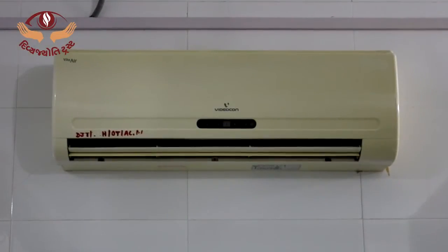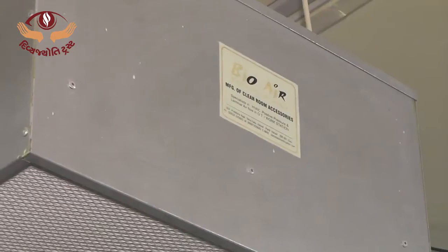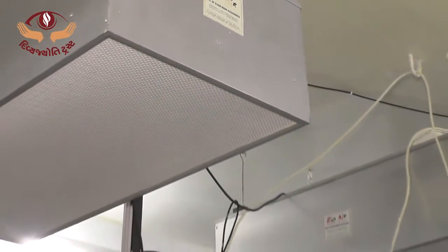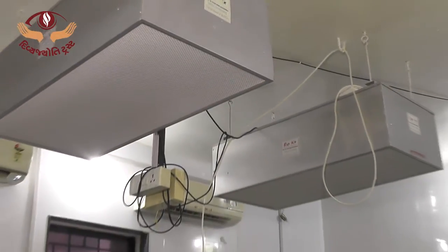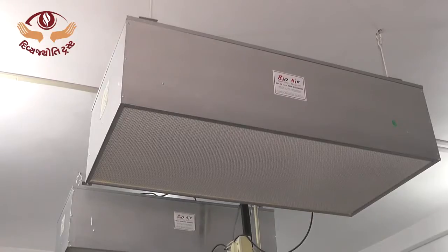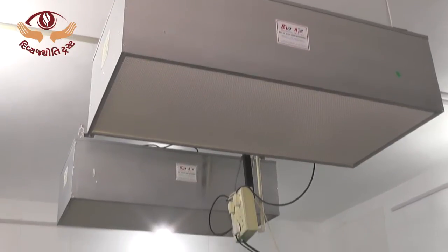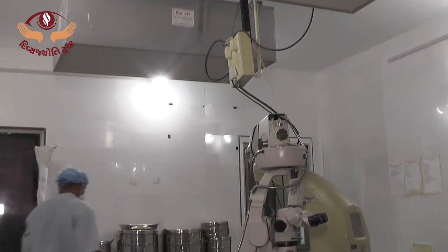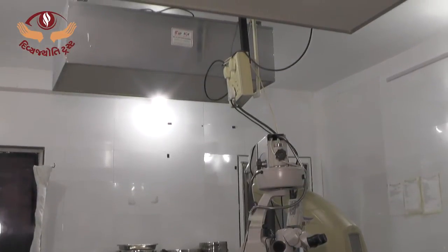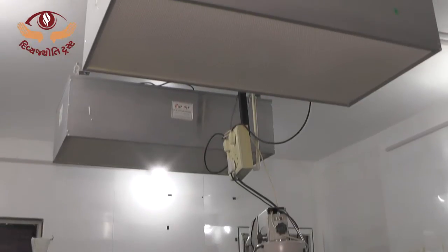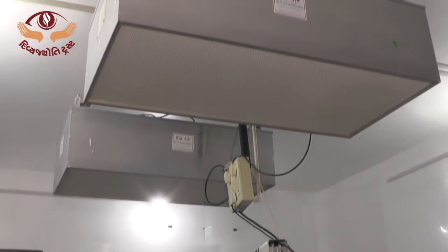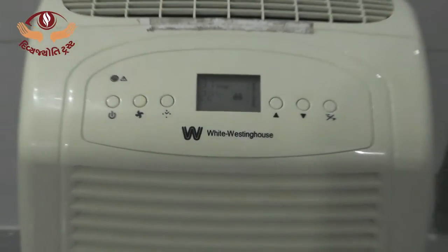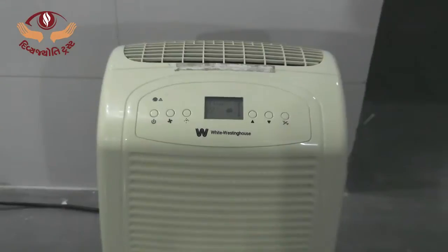Minimum 20 air exchanges per hour are ensured by split AC. Central AC with AHU is the best but very costly. NABH standard requires this. Sterile quality of air in the OT is better maintained by employing air cleaner, which should be turned on while the surgical session is going on. HEPA filter with filtering capacity of less than 0.3 micron is considered much better. Laminar airflow above the sterile field is also a good option if afforded cost-wise. Dehumidifier can be used to maintain humidity between 30 to 60%.